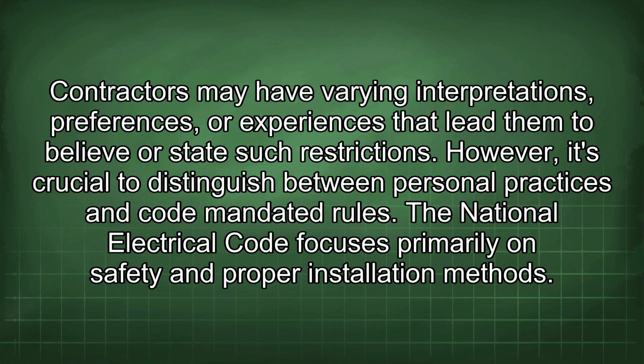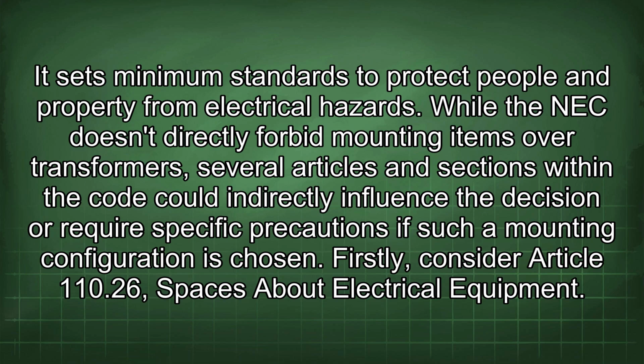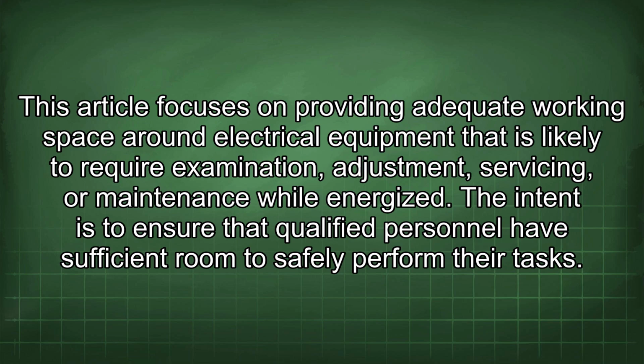The National Electrical Code focuses primarily on safety and proper installation methods. It sets minimum standards to protect people and property from electrical hazards. While the NEC doesn't directly forbid mounting items over transformers, several articles and sections within the code could indirectly influence the decision or require specific precautions if such a mounting configuration is chosen. Firstly, consider Article 110.26, Spaces about electrical equipment. This article focuses on providing adequate working space around electrical equipment that is likely to require examination, adjustment, servicing, or maintenance while energized. The intent is to ensure that qualified personnel have sufficient room to safely perform their tasks.